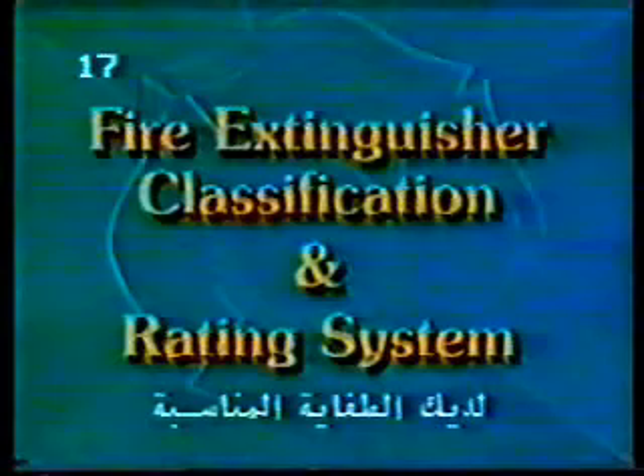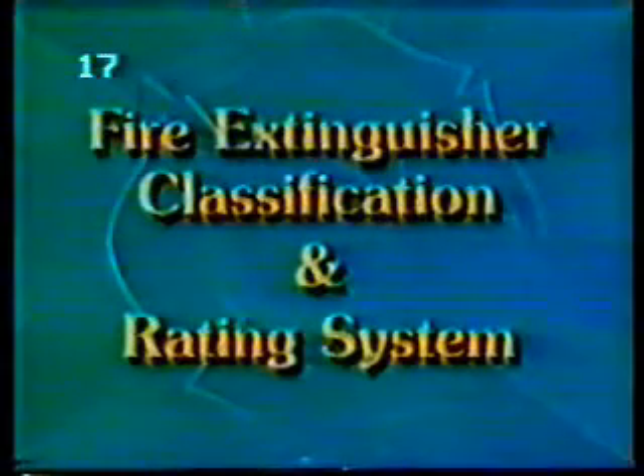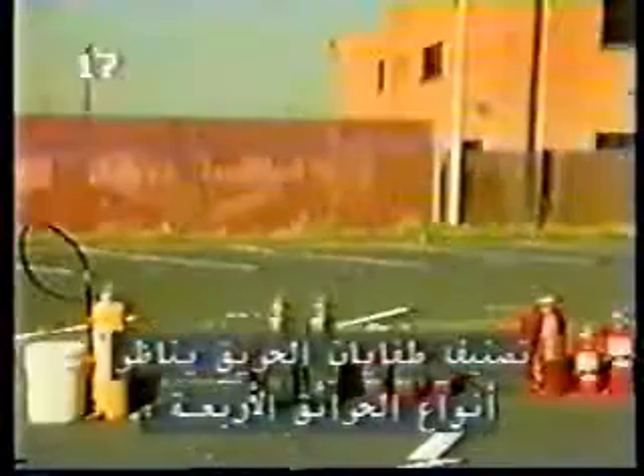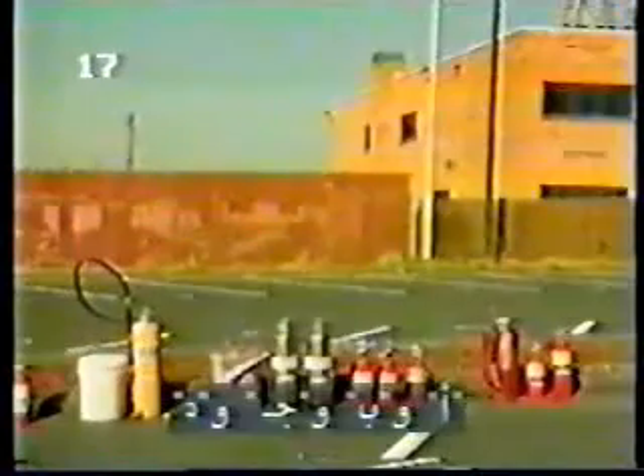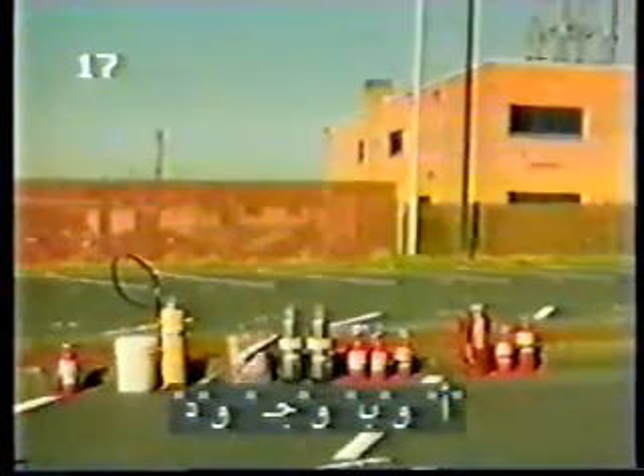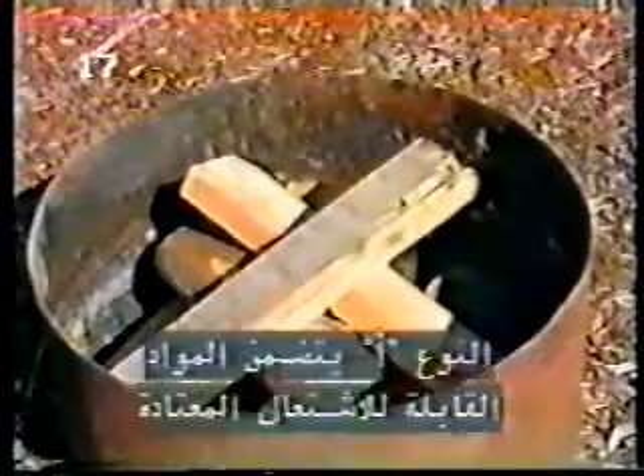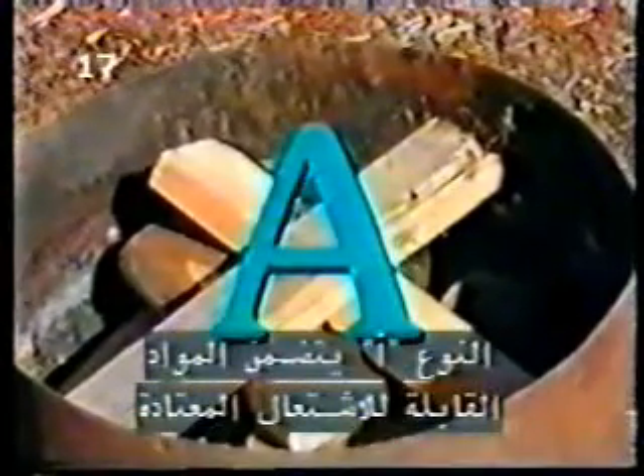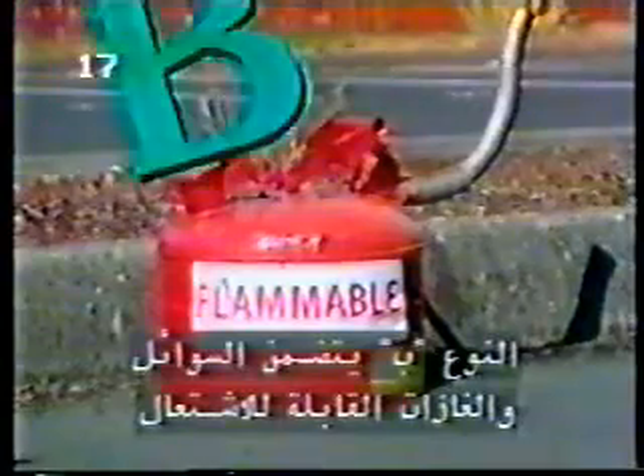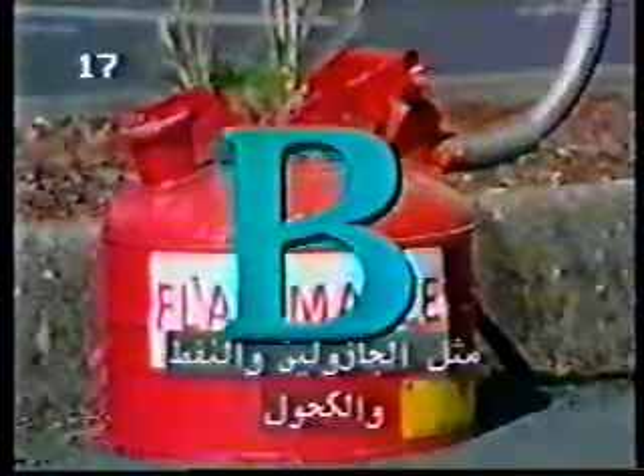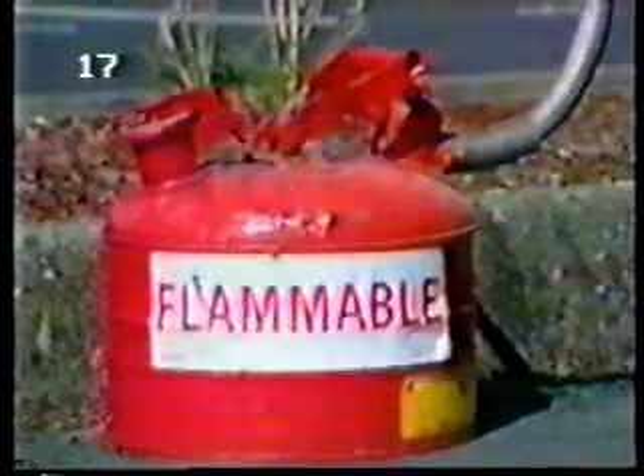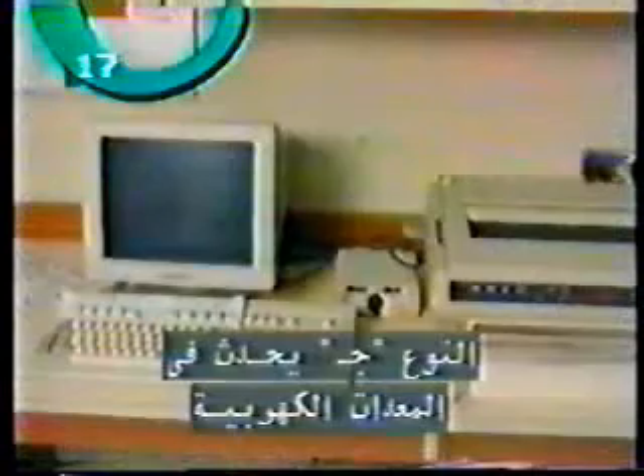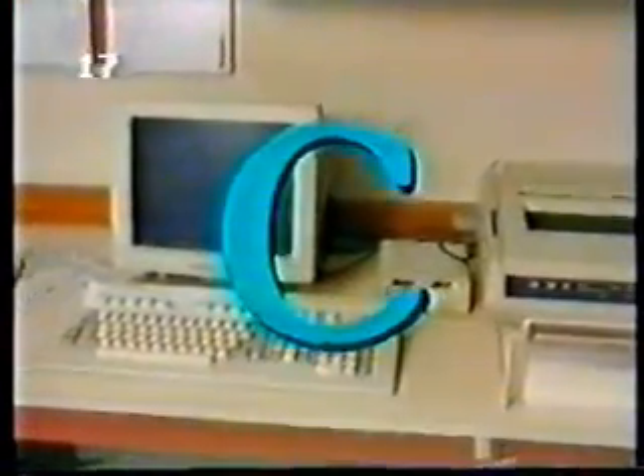The classification of fire extinguishers corresponds with the 4 classes of fire: A, B, C, and D. Class A fires involve ordinary combustibles, such as paper, wood, cloth, and many plastics. Class B fires involve flammable and combustible liquids, such as gasoline, oil, and alcohols. Class C fires are found in energized electrical equipment, such as household appliances, computers, or overhead transmission lines. And Class D fires involve combustible metals, such as aluminum, magnesium, and sodium.